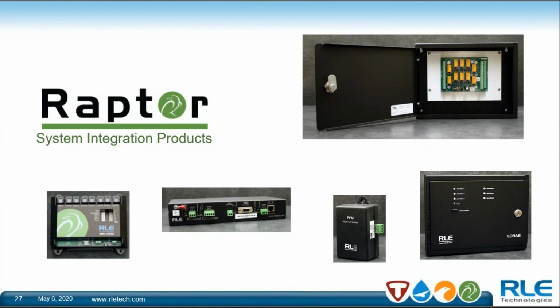The guy in the middle there is the protocol converter. This is a signal annunciation that is going to take, I know you're all in all kinds of mechanical rooms and you have equipment that talks Modbus, and sometimes you're trying to get it into SNMP. We have a protocol converter that would take that signal, bring it in Modbus, push it out SNMP, or maybe you bring it in BACnet and need to push it out SNMP or Modbus or one of those combinations. So there's certainly that.